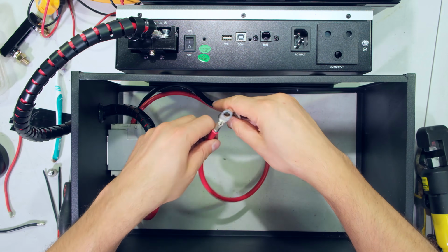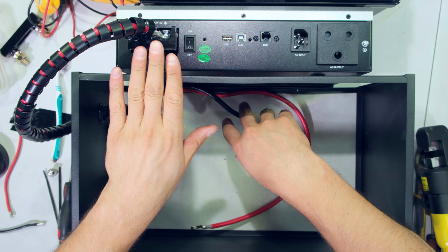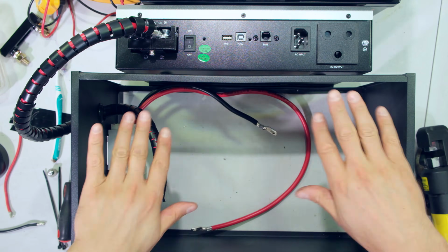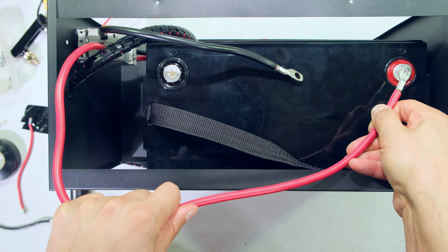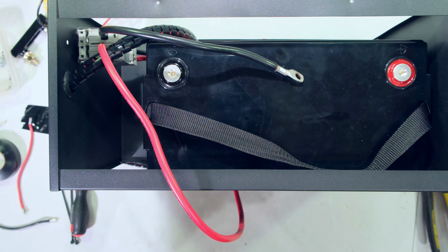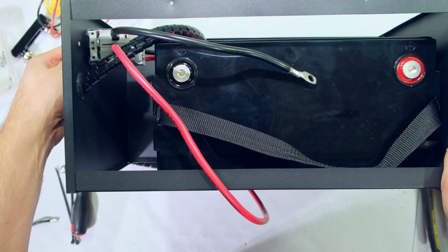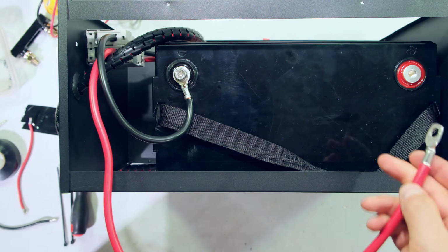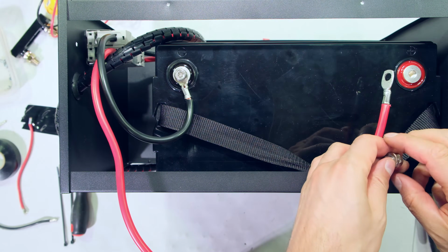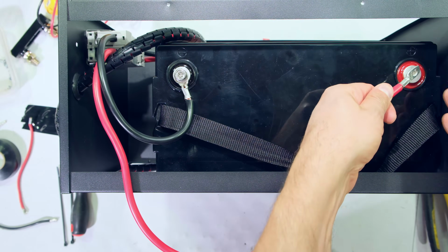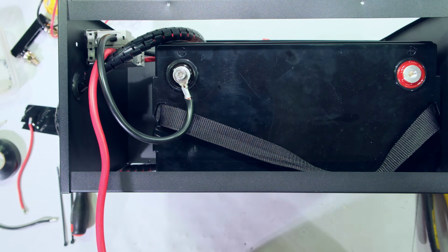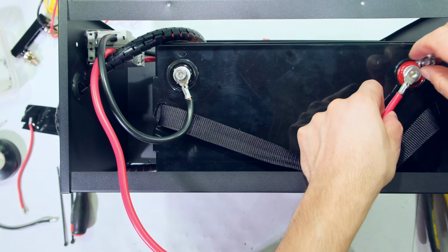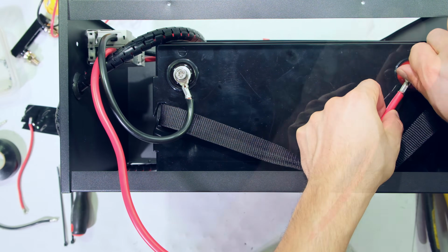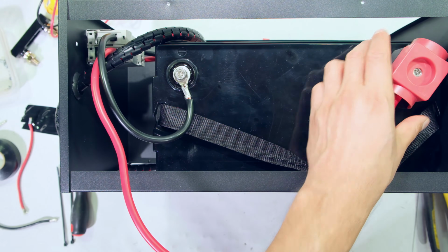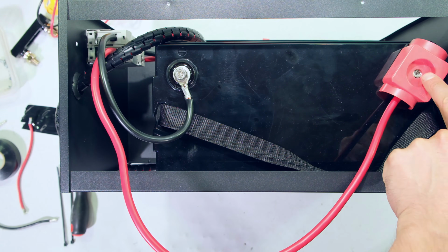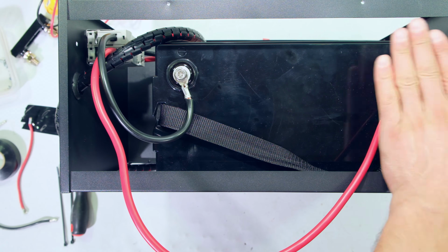Now, the last step is to connect the battery. So in the meantime, I'm just going to disconnect this so I can get full view of the battery compartment. Now I can put these cables directly to the terminals. Just a few safety precautions before I do that. I make sure the circuit breaker is down. Right, now for the positive lead, we need to put something around here because just now the battery bumps onto the metal or something like that. So the positive lead has to be encased in a resin of sorts. For example, I could put something like this, and then I can put that screw through this top. Therefore, this can never touch the chassis.